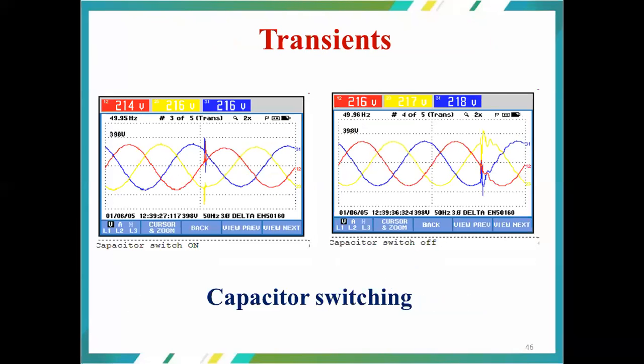And this one is the transient, due to the surges of capacitor switching, inductive switching, or any switching of the power electronic components. You may have short duration voltage spikes due to this large load switching and the nature of the load. It is a microsecond or even millisecond phenomenon, which is very injurious to the system.